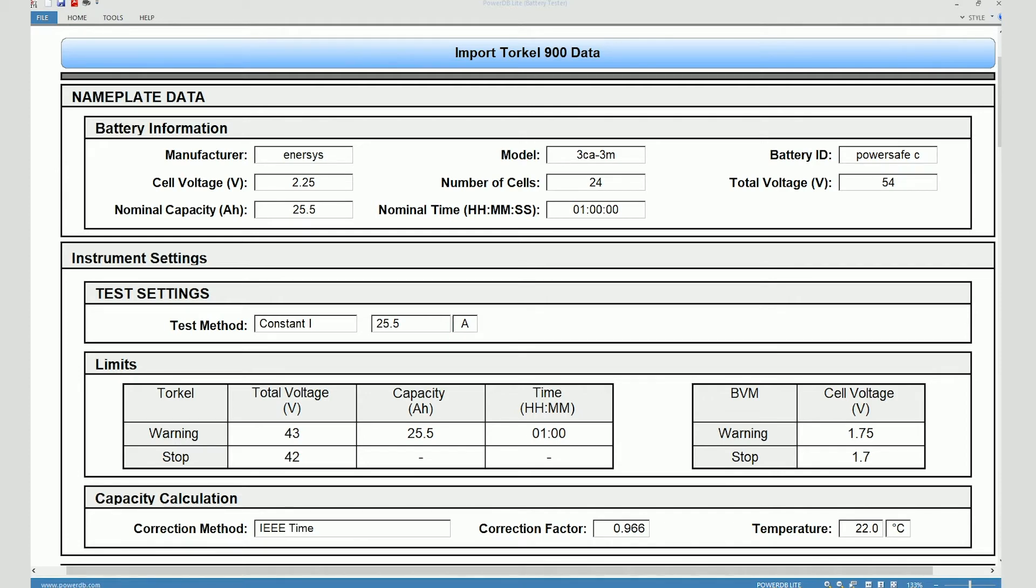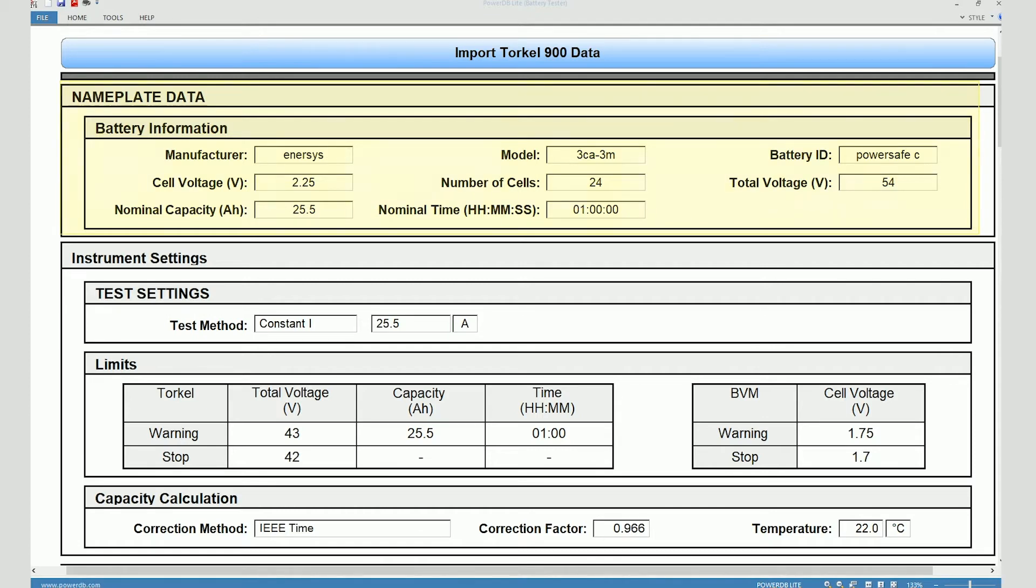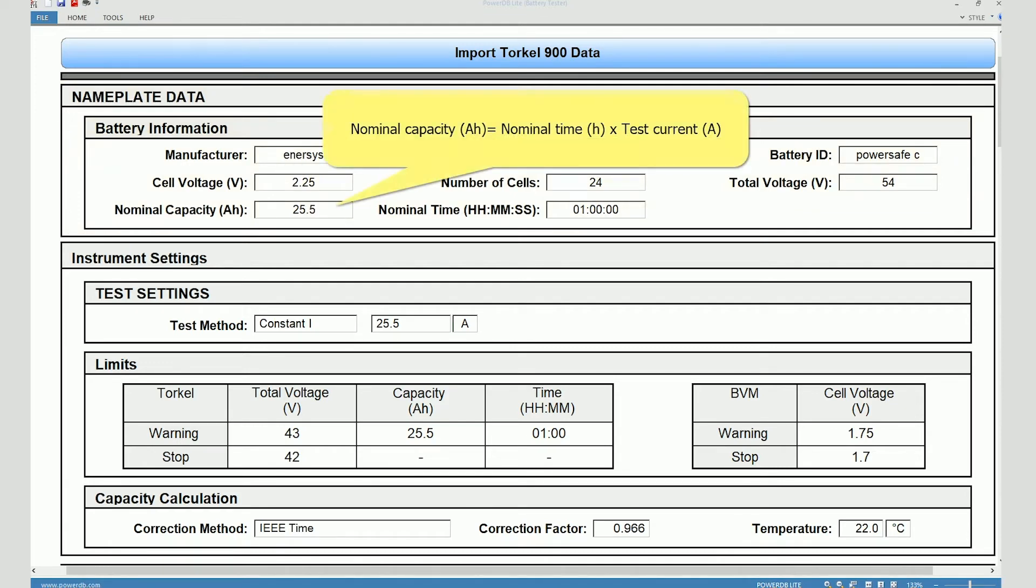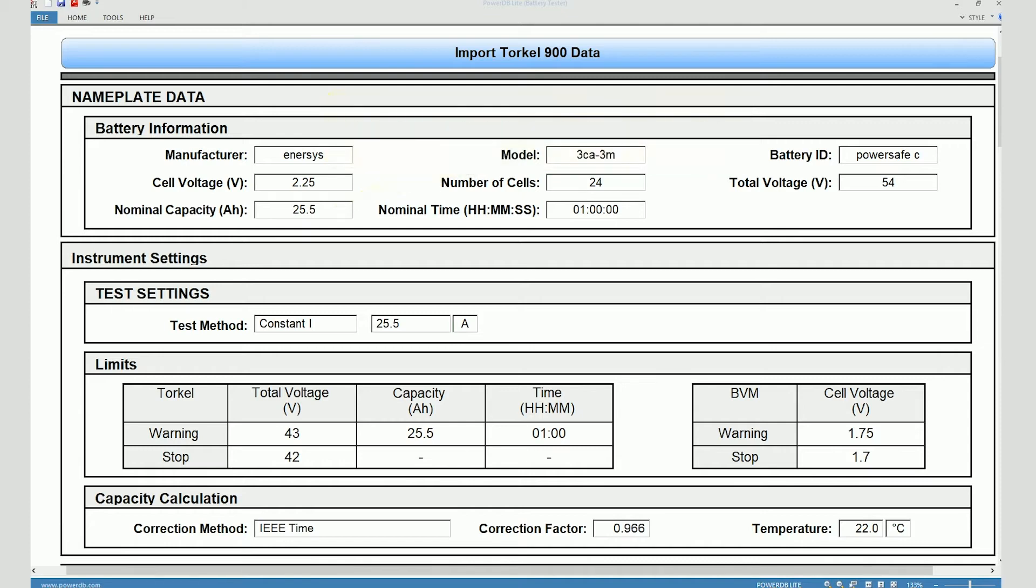So here you can see the nameplate information of the battery which includes manufacturer, model, battery ID, the cell voltage, number of cells on the string, the overall voltage, the nominal capacity which is not the rated capacity of the battery but it's the capacity in terms of the test parameters which is basically test duration times the test current. The nominal time, the intended test duration, is one hour.